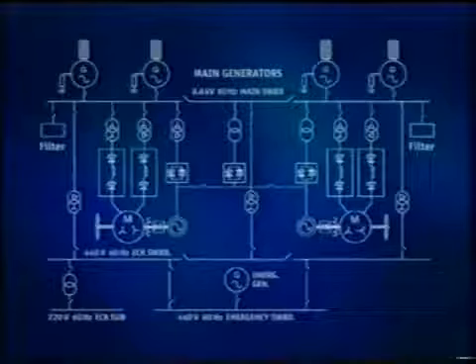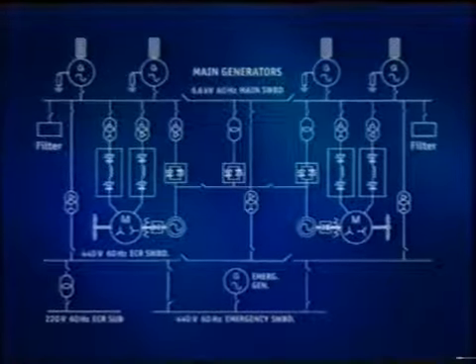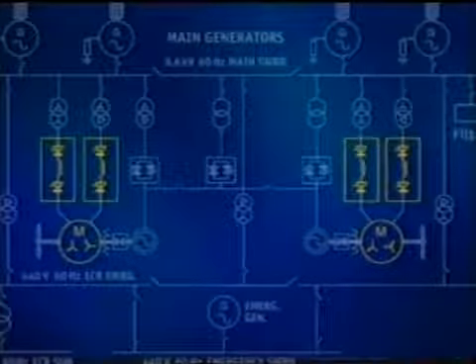Marine propulsion motors are almost universally AC. In some cases, the chosen configuration is induction motors running at constant voltage and frequency, linked to controllable pitch propellers. Some specialist vessels, such as cable layers and offshore drilling rigs, may use DC motor drives, but their power capability is limited by the low-voltage rotating commutator, which requires increased maintenance. A significant modern development is the use of variable speed drive technology. This entails the use of static converters feeding variable frequency AC to synchronous motors driving fixed pitch propellers.